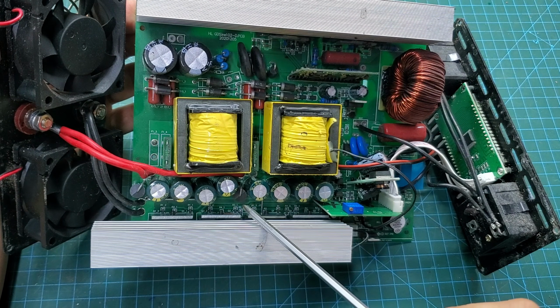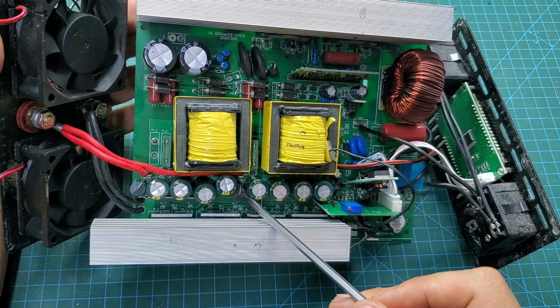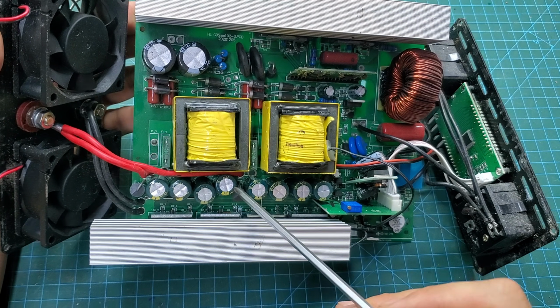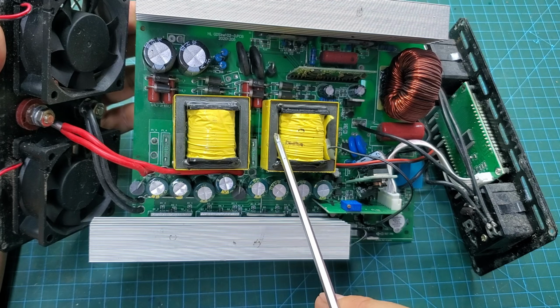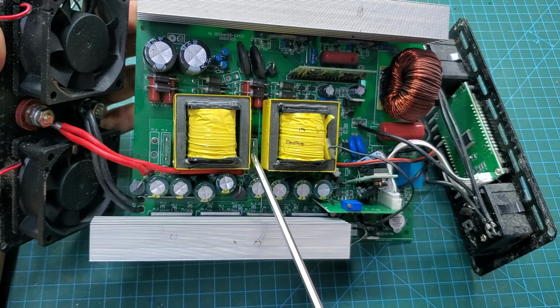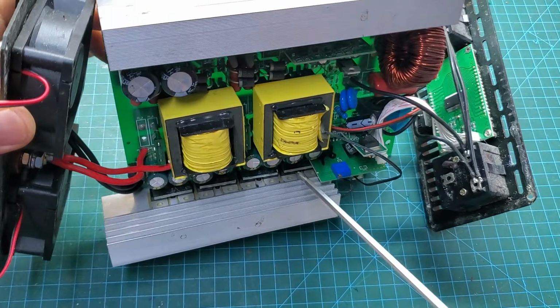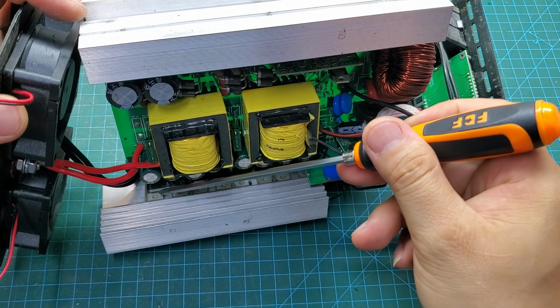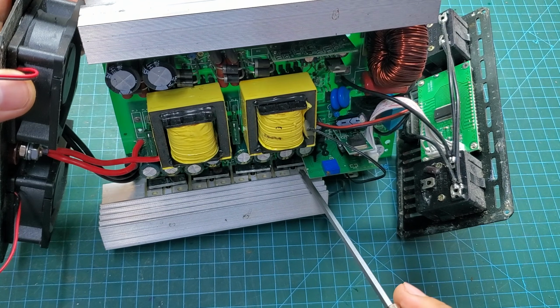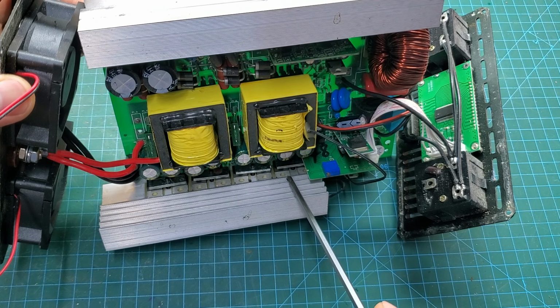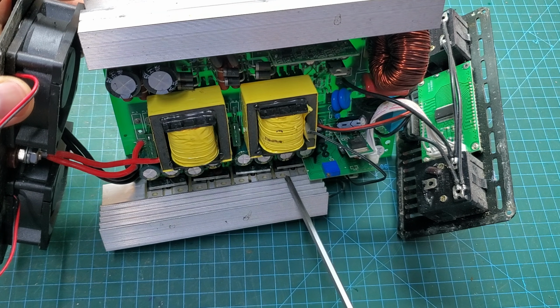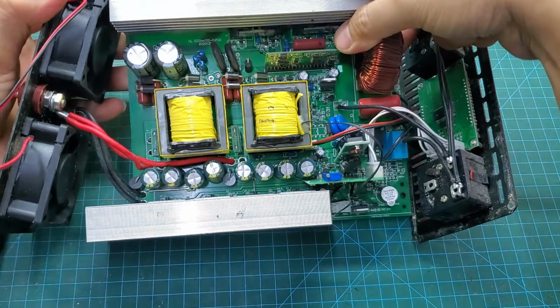This inverter uses 8 input filter capacitors. The reason for having so many is to reduce the overall ESR, which helps keep the capacitors cooler during operation. It has 8 MOSFETs, evenly distributed across the 2 switching transformers. Each transformer uses 4 MOSFETs, arranged in 2 legs. The MOSFETs are rated at 200 volts and 55 amperes.